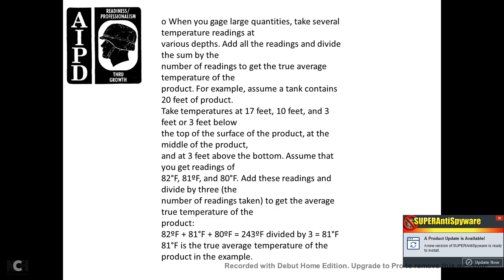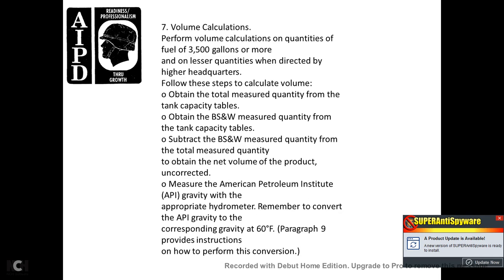When gauging large quantities, take several temperature readings at various depths. Add all readings and divide by the number of readings to get the true average temperature. For example, assume the tank contains 20 feet of product; take temperatures at 3 feet below the surface, at the middle, and at 3 feet above the bottom. If your readings are 82, 81, and 80 degrees Fahrenheit, add them: 82 + 81 + 80 = 243, divided by 3 = 81 degrees Fahrenheit — the true average temperature of the product.